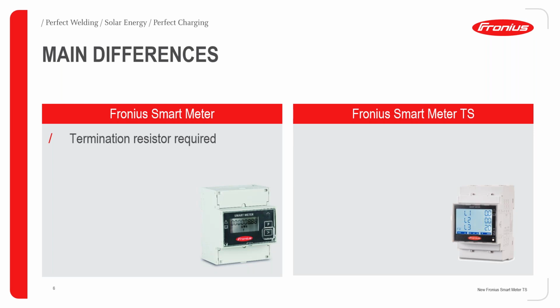So the main differences: a terminal resistor is required for the old Fronius smart meter. I believe there are no more of the old Fronius smart meters available in the market. In case it is available, you can still use it, just make sure of the terminal resistor. There will be a physical terminal resistor in the old one, and in the new Fronius Smart Meter TS, you have to set it via a cable. You have to put a cable in between two points in the smart meter. So the resistor is inbuilt, you just have to bridge it.